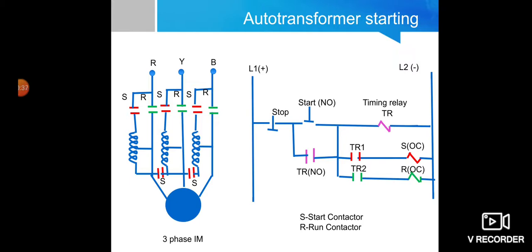This is a figure of auto transformer starting. The starting using 5-pole contactor is shown. The start contactor S has 5 poles. It connects the transformer to the line and closes its star point. The taps are normally for 50%, 60% and 70% of the line voltage. And the run contactor connects the motor stator winding to the full line voltage.